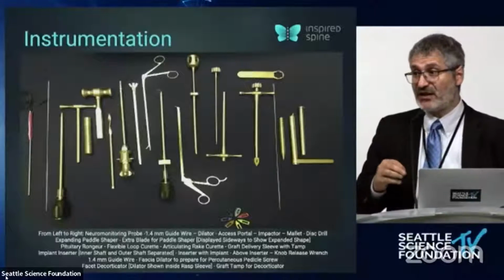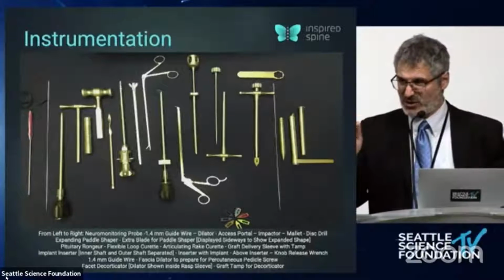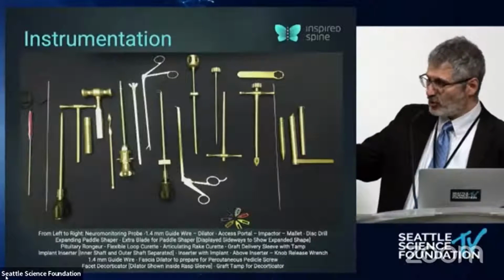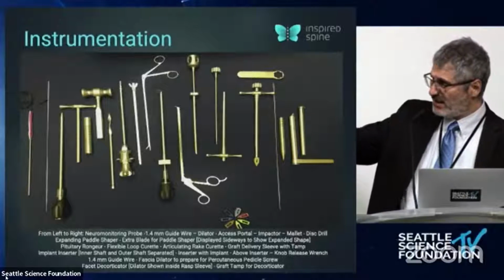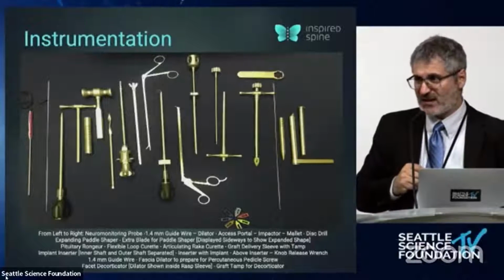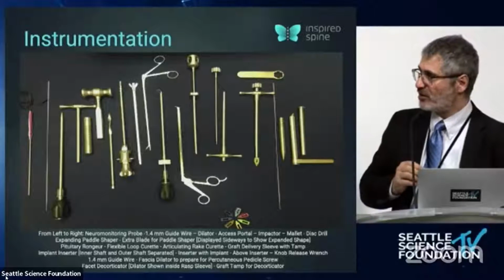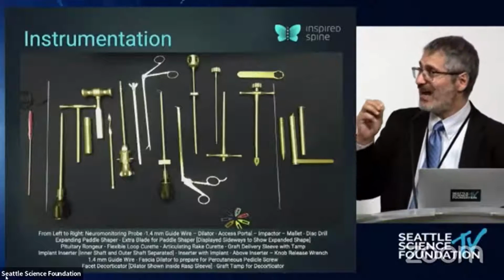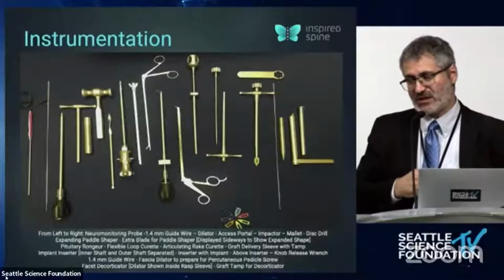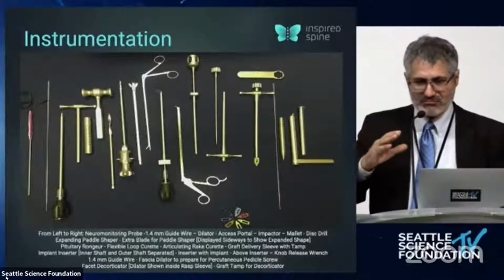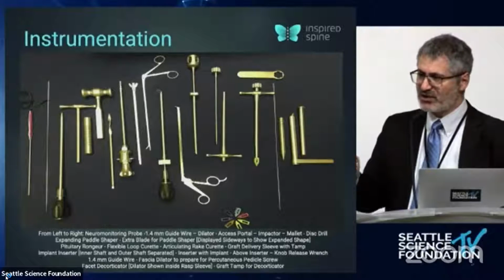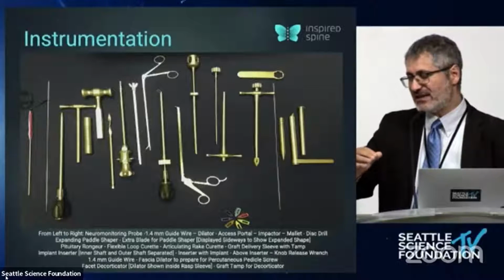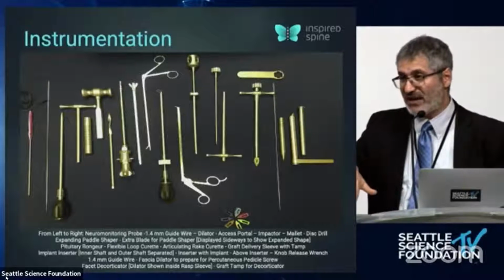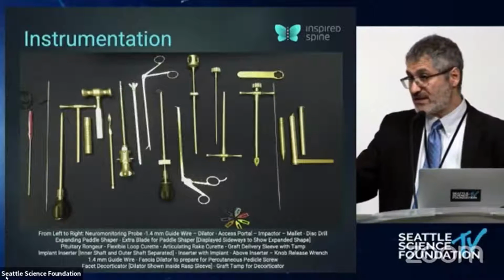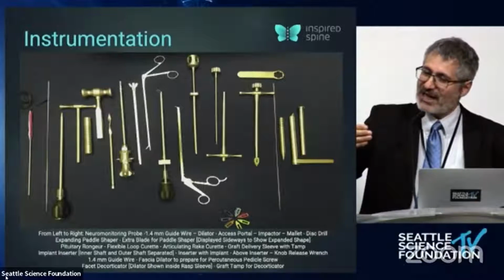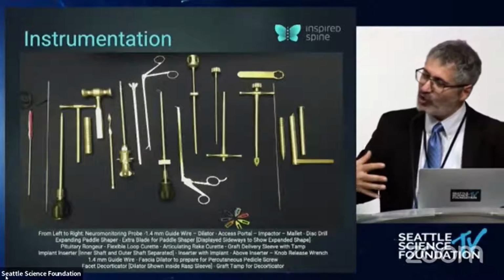The probe is Teflon coated, only the tip is available, so you're not dispersing energy and you're not shunting with the sleeve. Then the K-wire goes in through the sleeve of the neuromonitoring probe. Then the sleeve comes out. The dilation device goes in. Even in the most degeneratively changed disc, once you get the K-wire in, the dilator opens up Kambin's triangle as you go. We know that the nerve root is almost attached to the pedicle of the level above. So we are opening it as we go.